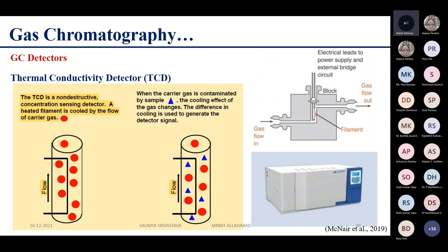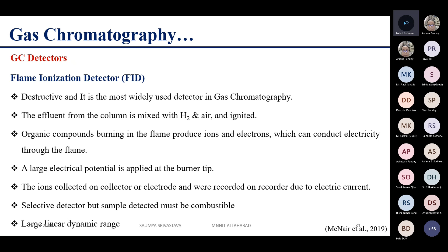Flame ionization detector is destructive in nature, and it is the most widely used detector in gas chromatography. The effluent from the column is mixed with hydrogen and air and ignited. The organic compounds burning in the flame produce ions and electrons, which can conduct electricity through the flame. A large electric potential is applied at the burner tip, and the ions are collected on the collector electrode and recorded on the recorder. It has a large linear dynamic range.